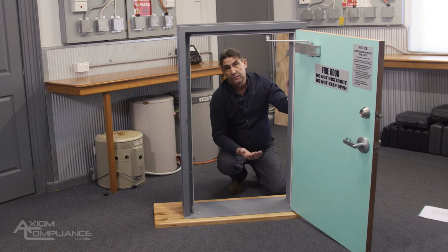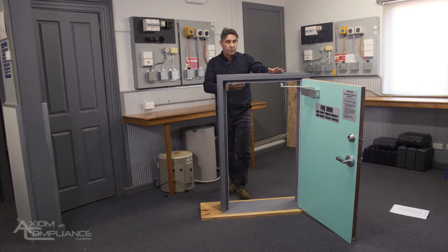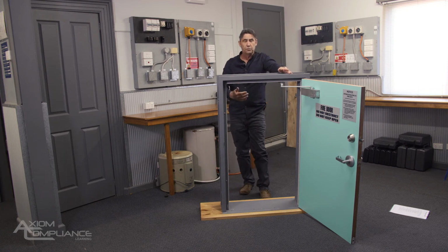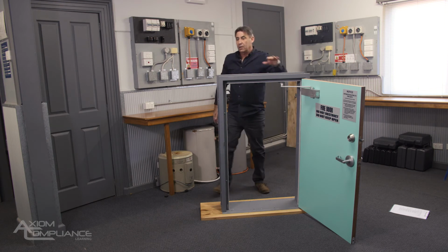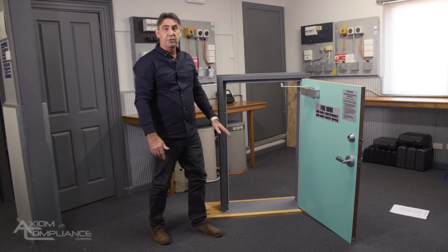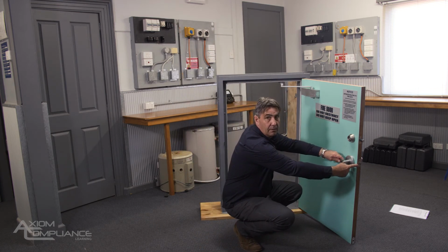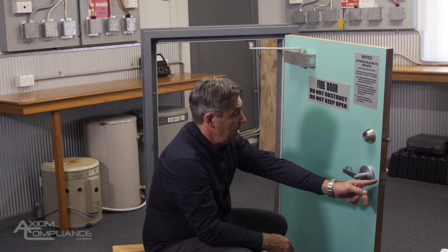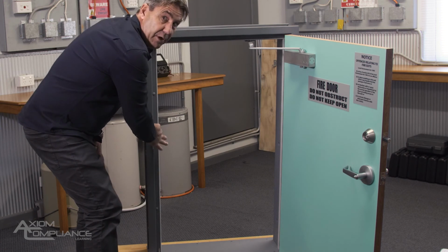We need now to close the door, and there's a check that we need to make on the handle. So remember that the door is opening into or out to an exit of some kind, so either an egress path or to the outside of an open area or an open space. So in actual fact, we're entering the door from this side. Now, one of the other checks that the standard requires us to make is that the distance between this handle and the door stop needs to be 35mm minimum between the edge of that door handle and the door stop. So the door stop would be this part of the door here.